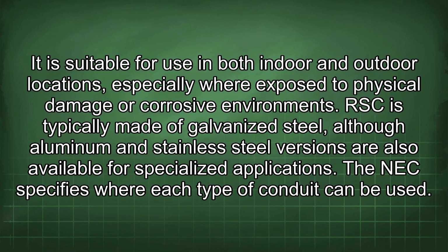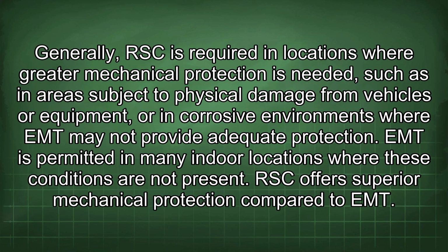The NEC specifies where each type of conduit can be used. Generally, RSC is required in locations where greater mechanical protection is needed, such as in areas subject to physical damage from vehicles or equipment, or in corrosive environments where EMT may not provide adequate protection. EMT is permitted in many indoor locations where these conditions are not present.